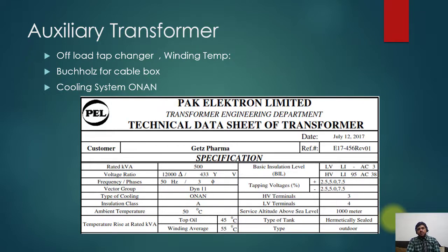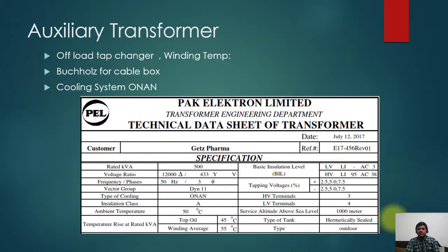Then there is a winding temperature indicator — mostly it is not available, but in some cases it is. Buchholz relay for the cable box may also be provided. The cooling system is oil natural air natural (ONAN); there is no forced cooling here normally. I have provided the nameplate for your study — the transformer is rated 500 kVA.